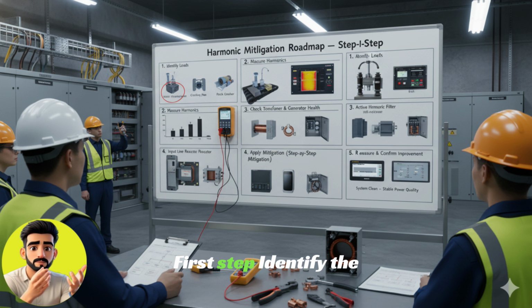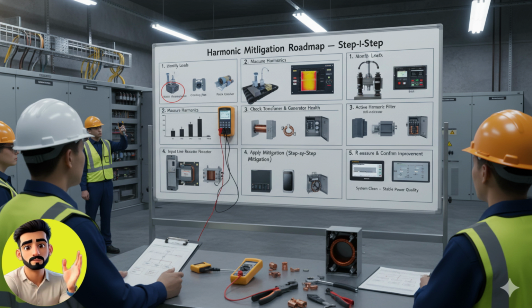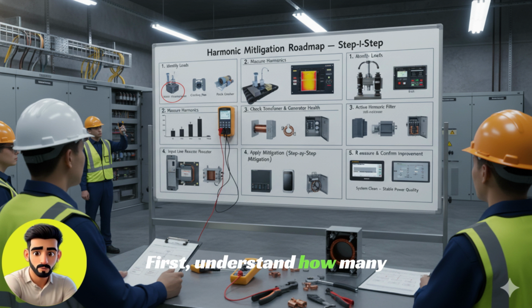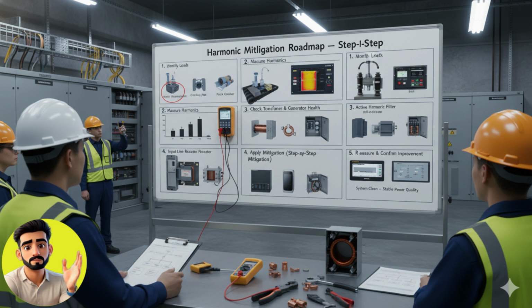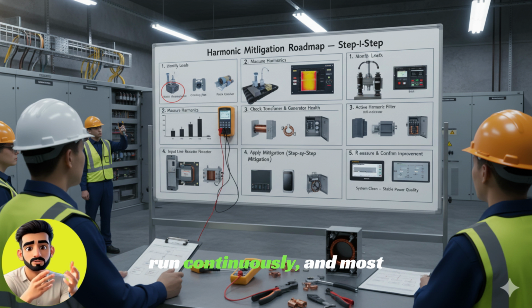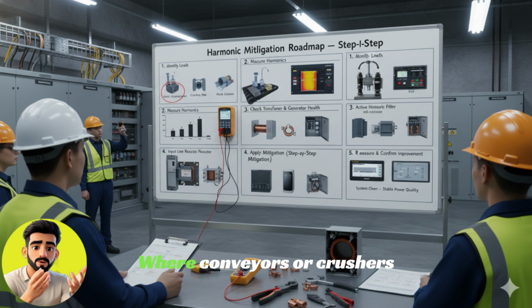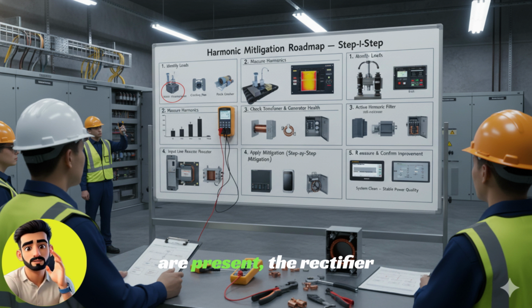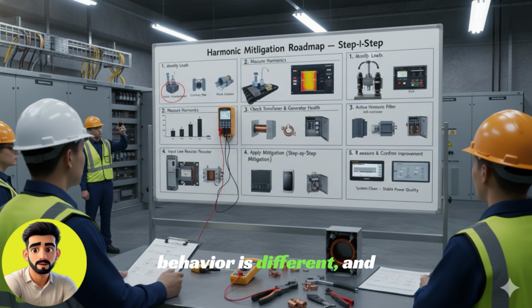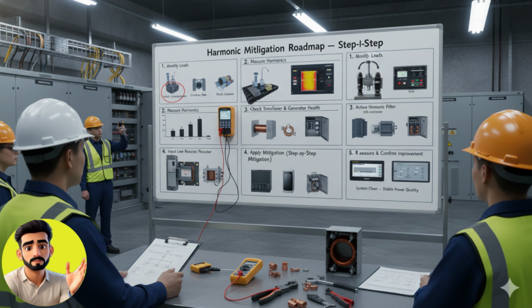First step, identify the nature of the load. First, understand how many drives are installed in the plant, what are their kilowatt ratings, and which loads operate continuously. Where centrifugal pumps and fans are present, drives run continuously, and most of the harmonic share comes from here. Where conveyors or crushers are present, the rectifier behavior is different and the distortion pattern varies. Understanding the nature of the load is the first step.